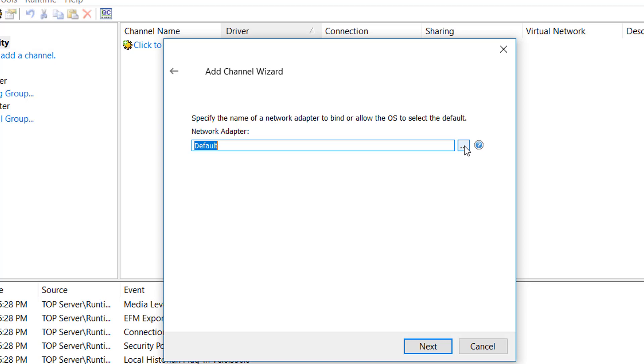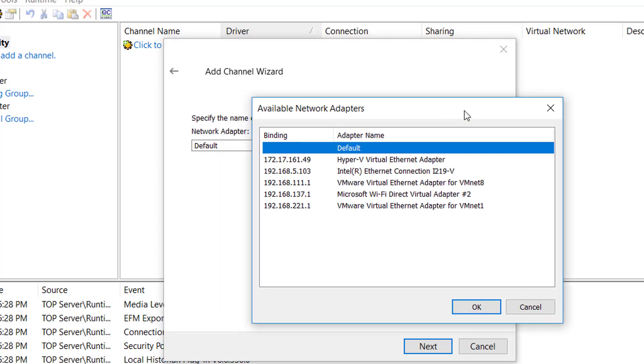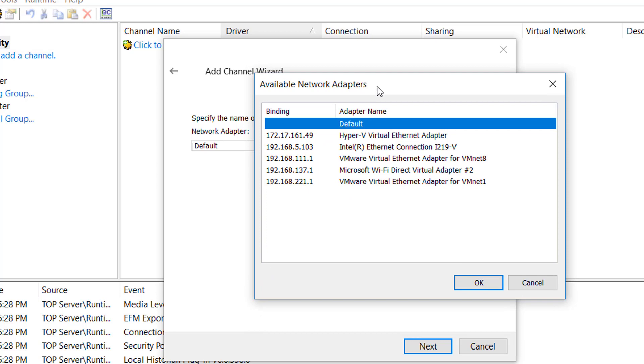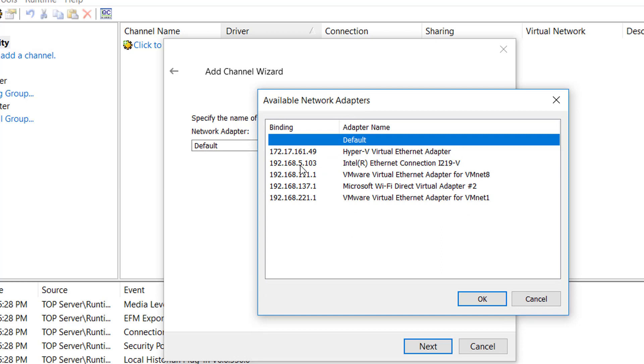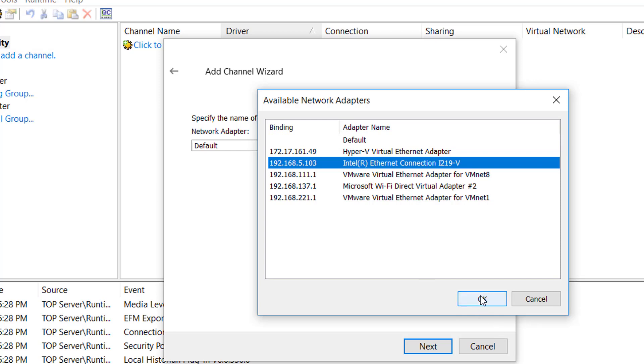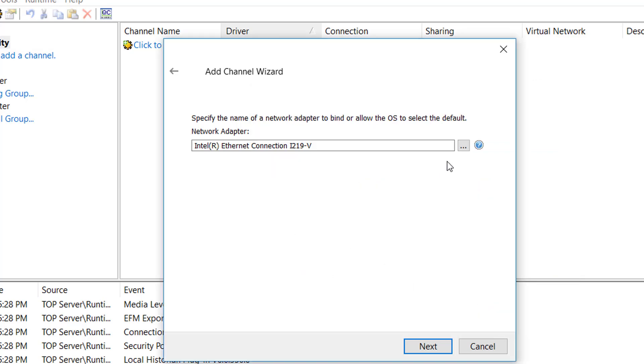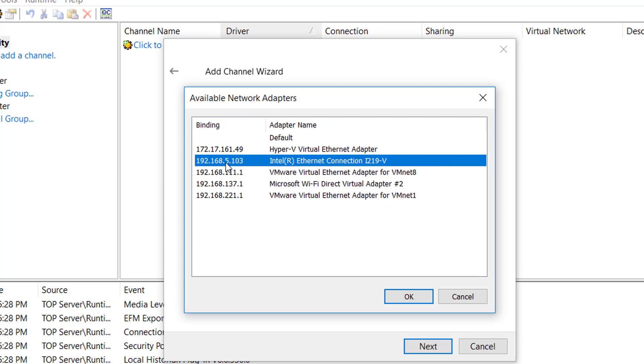Ordinarily you can leave the network adapter at the default and click Next, but with Omron FINS, as we discussed with multi-homing as a use case, if you multi-homed your NIC for multiple IP addresses, here's where you would click that button, go into Available Network Adapters, and your available multi-homed IP addresses will be listed. I would select the IP address I want to use for my connection to the Omron FINS controller. As you can see, the IP address for that NIC is 192.168.5.103 — remember that 103, as we'll see that when we configure our Omron FINS parameters in the device configuration. I'm going to click OK to select my network adapter.